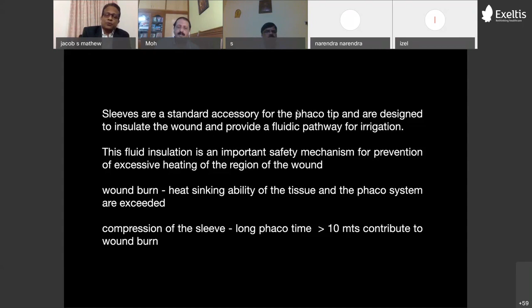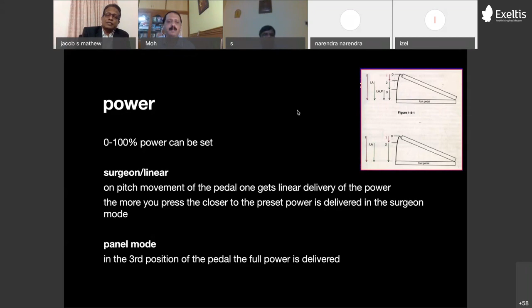So the power, as I mentioned, could be set from 0 to 100. Usually we go for something like 40%, or when a harder cataract comes, we raise it to 50 or 60 at the most. The present generation machines give excellent cutting, so you need much less power. And there are two kinds of settings for power that can be put. Normally we go for the linear mode, where the power keeps increasing as you press the pedal, and the final power that you have set on the panel will come at the extreme end of the pedal. Whereas in panel mode, in the third position of the foot pedal, you get the full power straight away. So as soon as you go into the third position, if you have kept a 40% power, you get it delivered fully, and that helps speed up your surgery. You are very sure where your power is getting delivered and how fast you're going to do it.